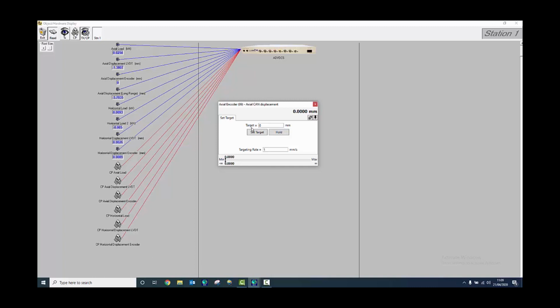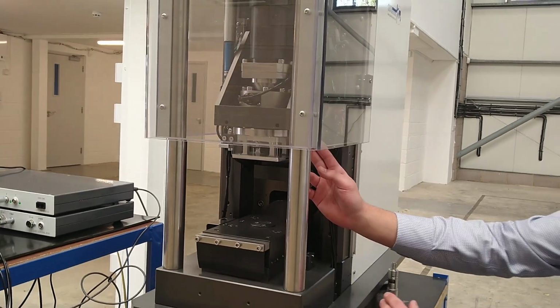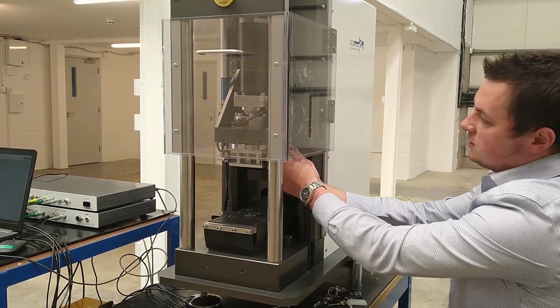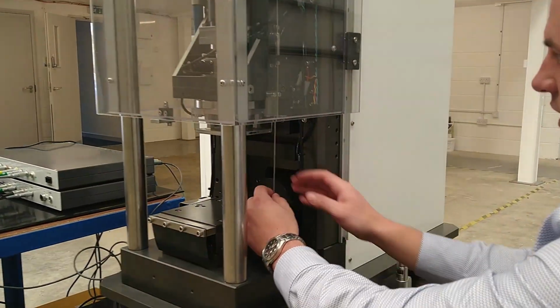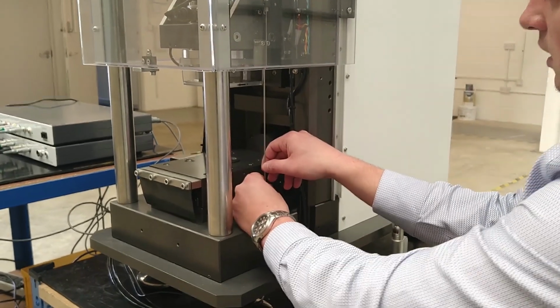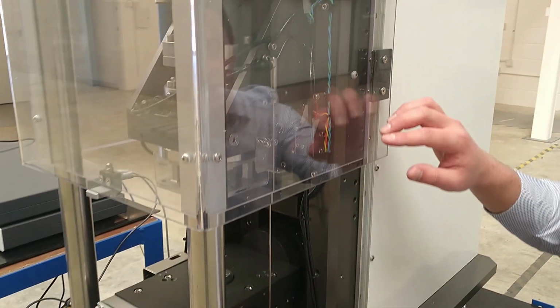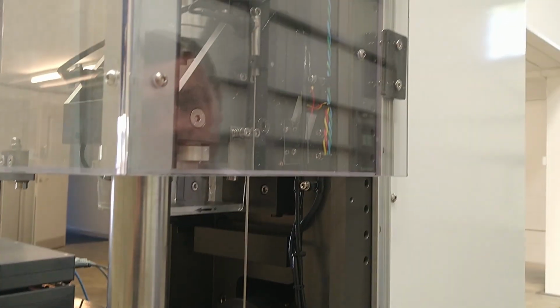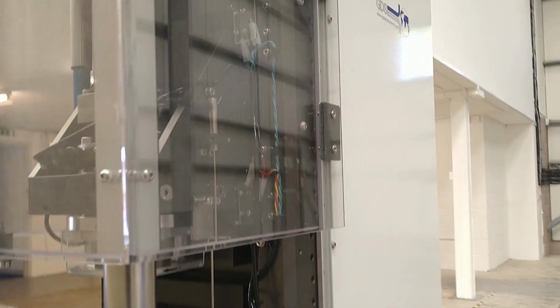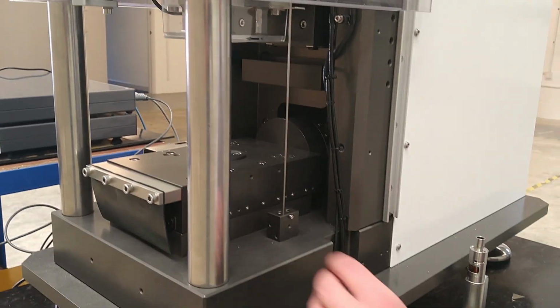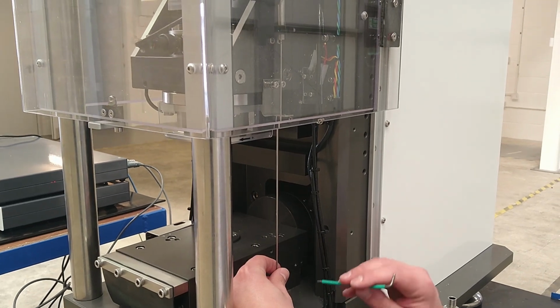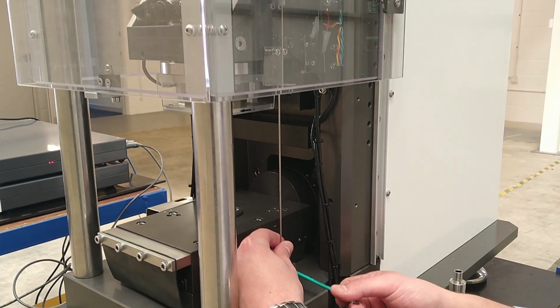So now to just double check the transducers, drop the armature from the vertical LVDT. There's a holding bracket that just slides. It's just spring loaded to the body of the carriage, and then I can move the LVDT down. If you look at the LVDT, you'll see 3 lines that mark the top position, the middle, and the maximum position. So I'll position it somewhere closely to the middle and tighten my screw. So position it somewhere close to the middle and tighten the screw to hold the armature in place.